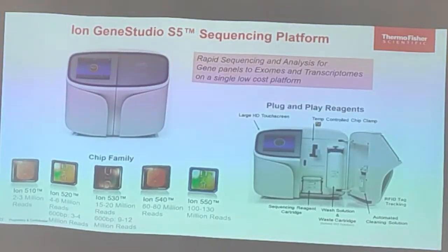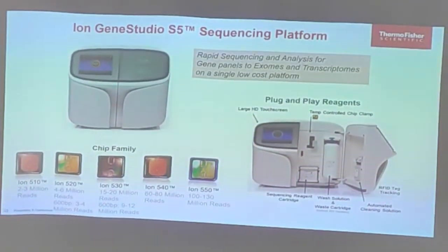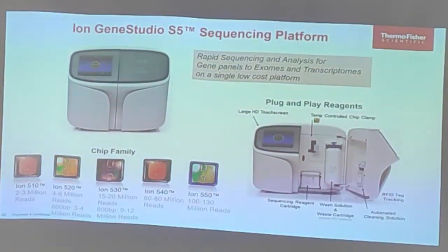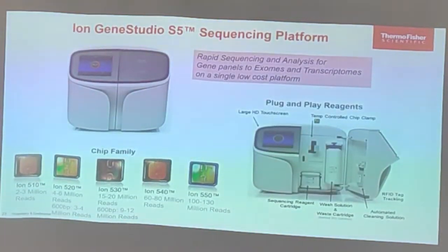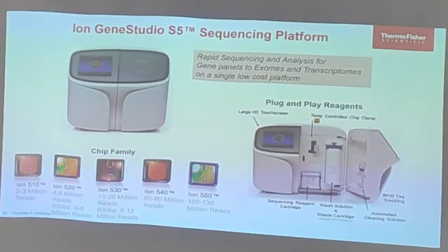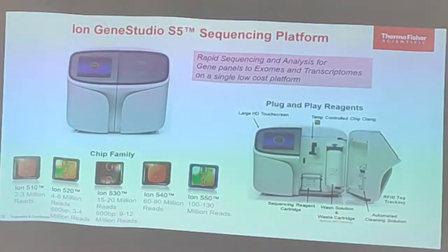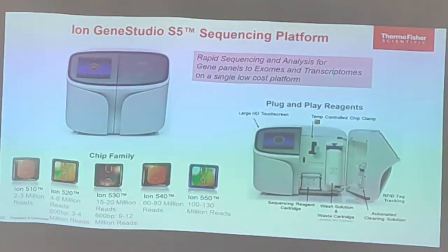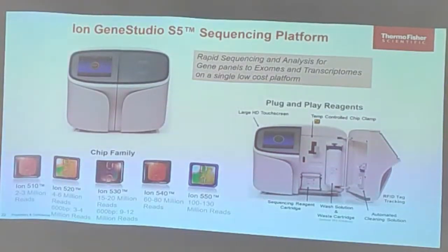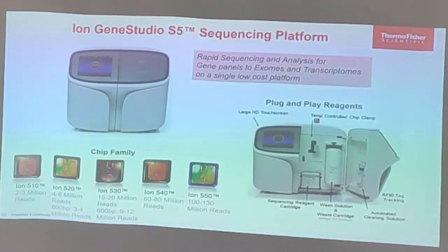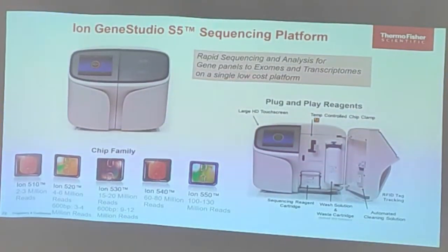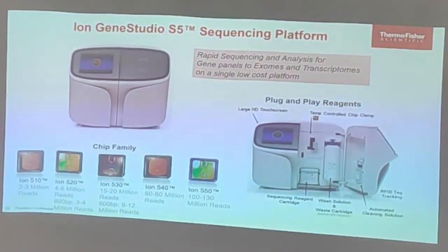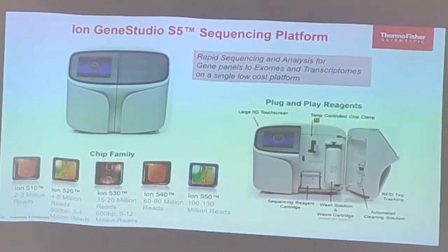We're going to use this 2 to 3 million reads. These are very low, meaning if you have a lesser sample size and very small genes, say only BRCA you want to sequence, certain mutations. So this machine is actually very versatile. It is a medium throughput instrument, but you can use it like a personal machine. It is also used with diagnostics. So you have flexibility in the run protocol. Very small or medium experiments can be done. That's why one instrument can cater to all types.